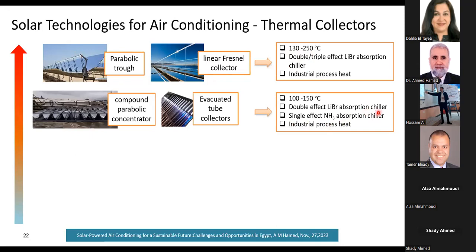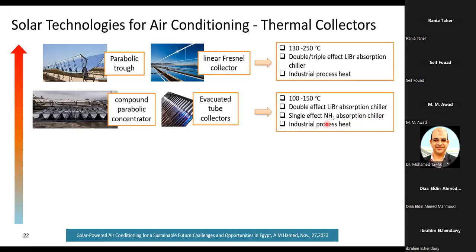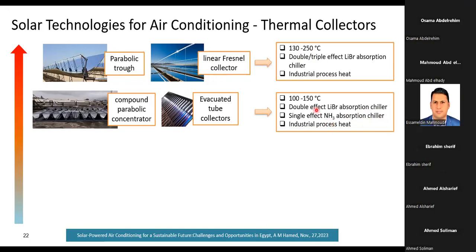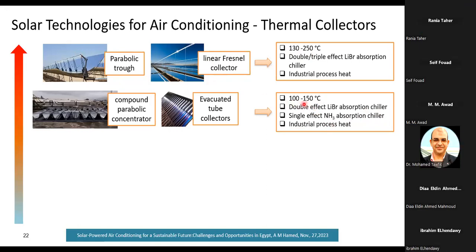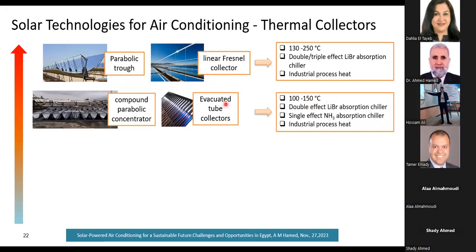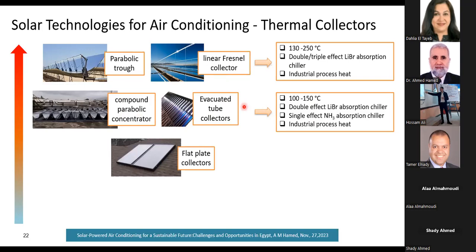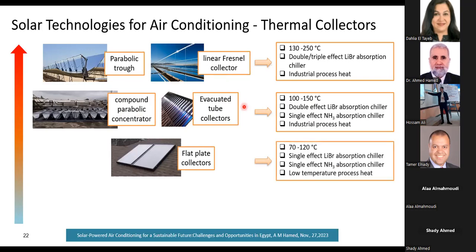The second example is the double effect lithium bromide absorption chiller, and single effect at the same time, using ammonia or water lithium bromide. In this case, the temperature level required is between 100 and 150 degrees Celsius. This system can be powered by using either a compound parabolic concentrator or an evacuated tube collector. The conventional flat plate collector can collect energy and give temperatures lower than the other two types, from 70 to 120.